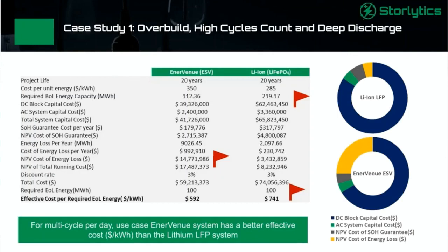Something to note here: for the lithium system, the yellow portion, which is the energy loss, was not as impactful - it was a small portion of the overall cost. Most of the cost was incurred by the cost of the lithium batteries themselves. But for the Enervenue system, the overall DC block cost was less, but they have a significant portion of the cost due to the energy loss and the relatively low round trip efficiency.